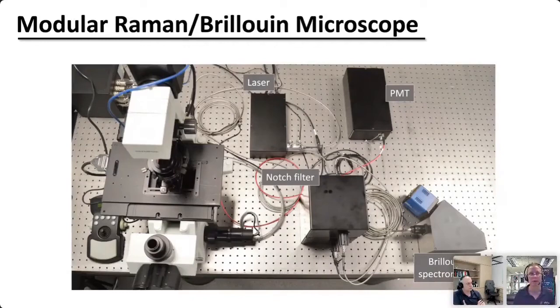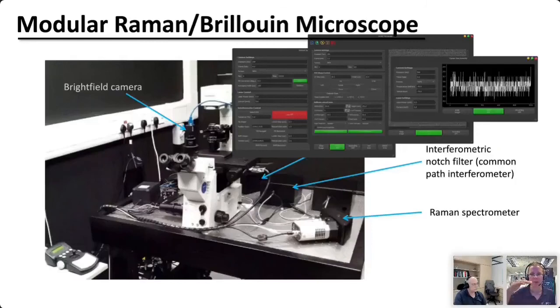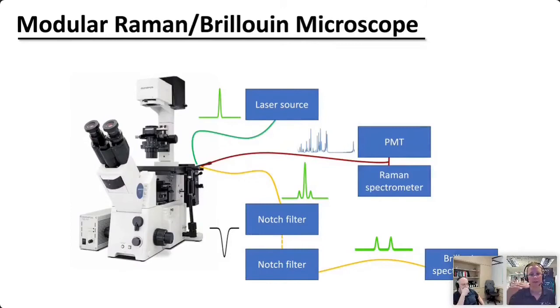A question about depth imaging: how do you obtain Brillouin images from different depths in the sample? The Brillouin microscope, because it couples into a single mode fiber, is a normal confocal microscope. You launch light from a single mode fiber and couple back into a single mode fiber — so it is basically a normal confocal microscope but with a fancy detector.